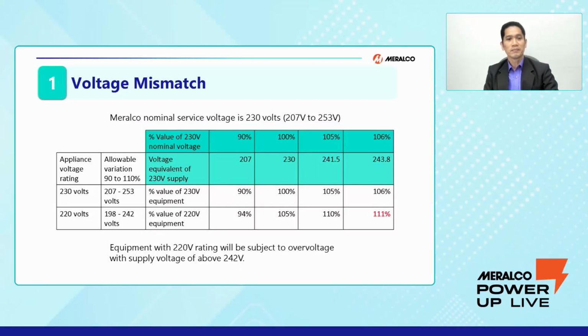To further explain, we can see here in our table, at the leftmost side, the appliance voltage rating. We are going to compare the 230 volt and the 220 volt rated equipment. The shaded cells on the horizontal are the 230 volts nominal voltage of Meralco and its equivalent supply voltage. The allowable voltage variation for 230 volts is the same as the supply voltage of Meralco at 230 volts, so there is no problem or concern, it is matched. Whereas for the 220 volt equipment, the allowable variation is from 198 up to 242 volts.